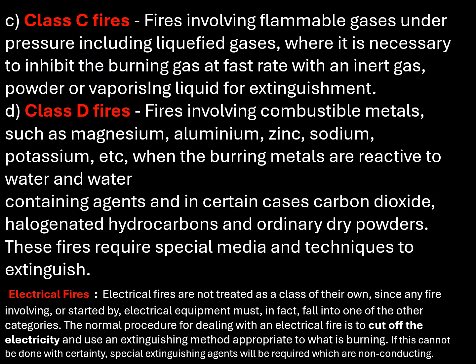Friend, we have seen fire in solids, fire in liquids, fire in gases, that is the third type, and type 4 is in combustible material. In other codes the world over, there is another type of fire, which is electrical fire. National Building Code 2016 does not recognize this as a separate fire type, because electrical fires are not treated as a class of their own, since any fire involving or started by electrical equipment must in fact fall into any one of the other categories once the electric switch is made off.